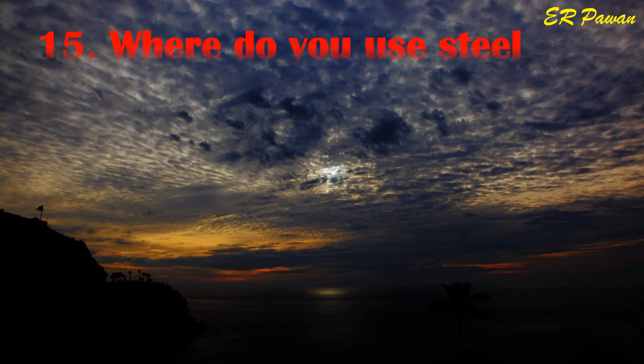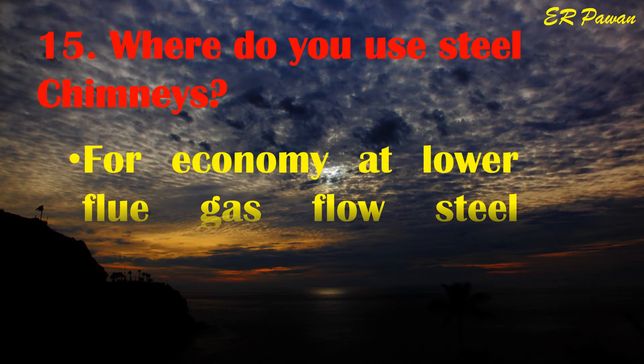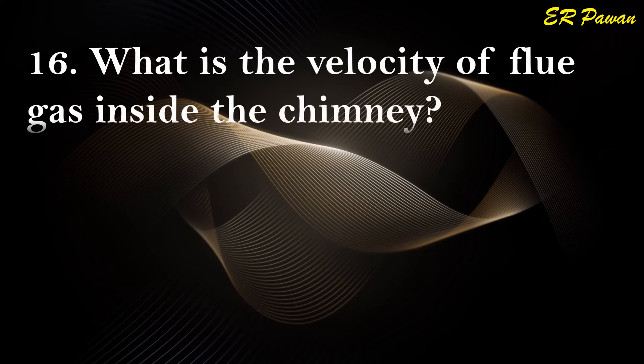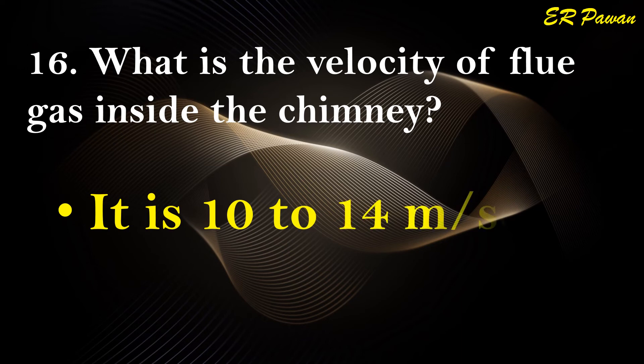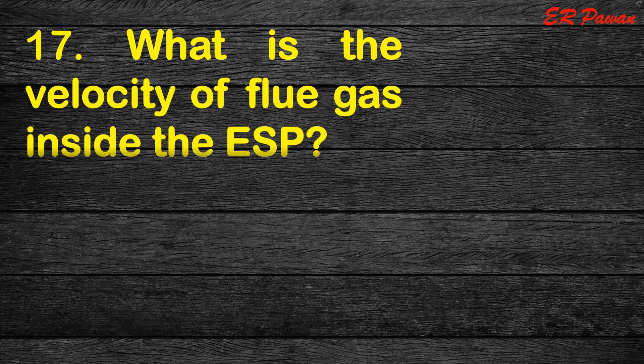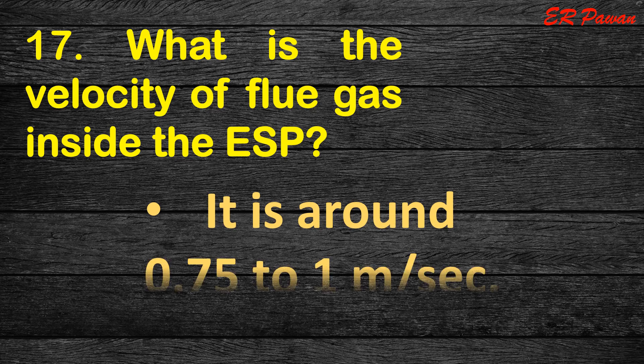Question 15: Where do you use steel chimneys? For economy at lower flue gas flow, steel chimneys are more preferred. Question 16: What is the velocity of flue gas inside the chimney? It is 10 to 14 meters per second. Question 17: What is the velocity of flue gas inside the electrostatic precipitators? It is around 0.75 to 1 meter per second.